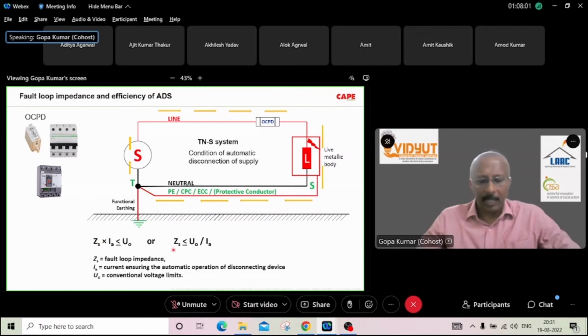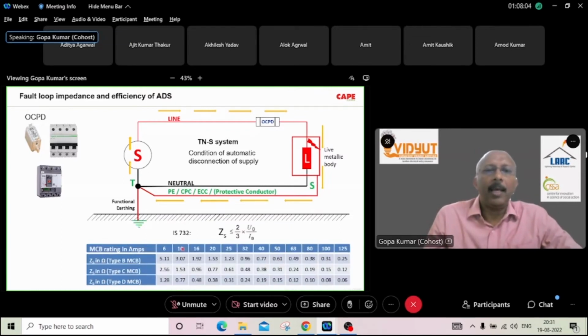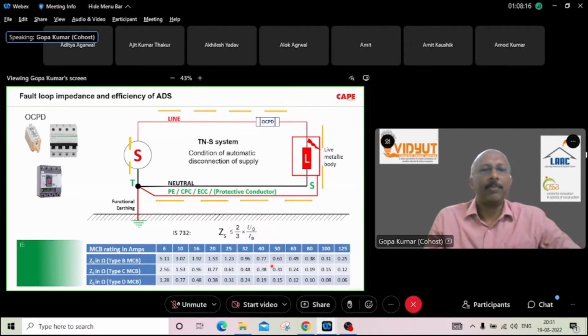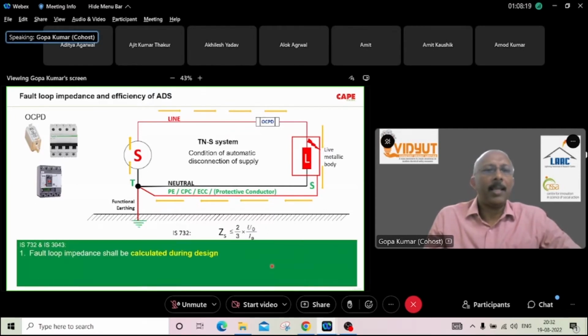These calculations are given in the upcoming National Electrical Code. We are trying to simplify it again. We have made the calculation for different types of MCB, what kind of fault loop impedance is desired for each and every case. Now, please understand that all these standards, the Code of Practices of India, IS 732, IS 3043, the National Electrical Code of India, say that fault loop impedance shall be calculated during design. Every circuit, you are supposed to calculate the fault loop impedance during design.